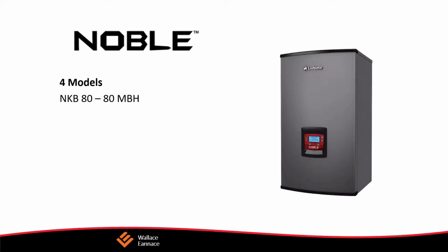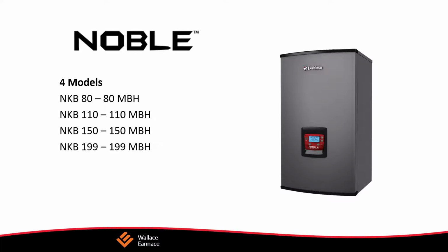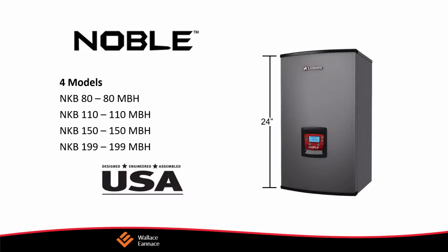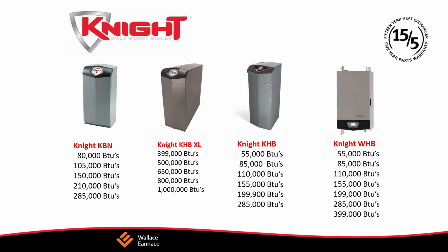the heating load. So one of the things we have to consider is that often we are designing for the domestic hot water load, and then we're also balancing the situation to get the hydronic heating load to operate in an efficient place. Once again, we said 35,000 BTUs for the heating load, but that's on the coldest day of the year. Most of the time, this is going to be running at about half of that, which is 17.5 or 15,000 BTUs. So ideally, I'd want a boiler that would put out about 10,000 BTUs, yet could go up to about 100,000 BTUs. So when there's a domestic hot water call, it can produce 100,000 BTUs. When there's a heating call at 10,000 BTUs, I'm still able to operate in that range.